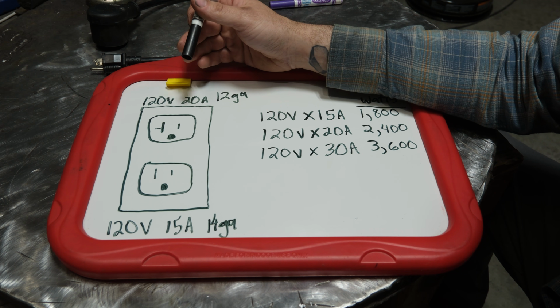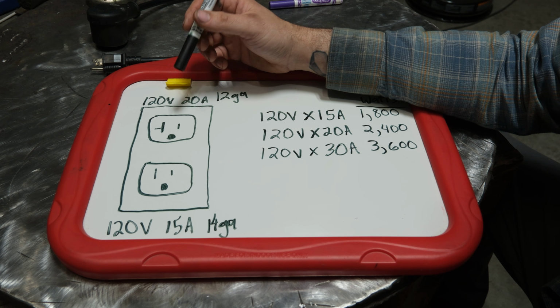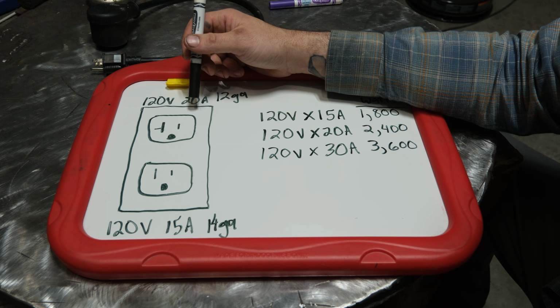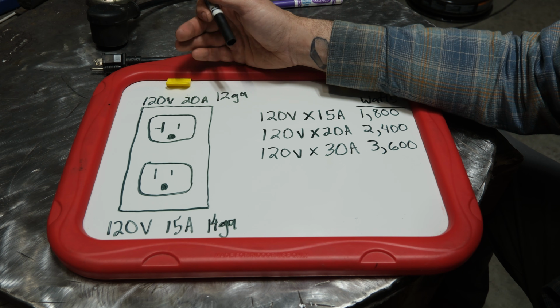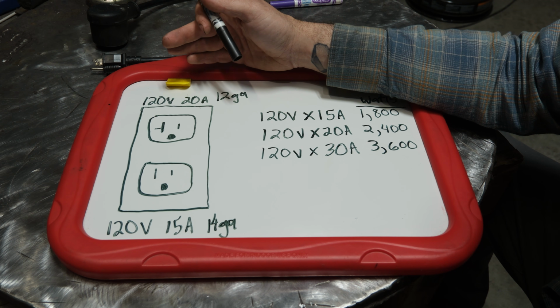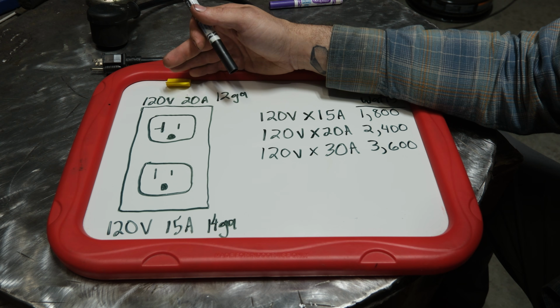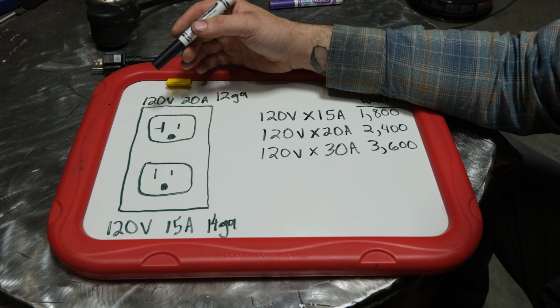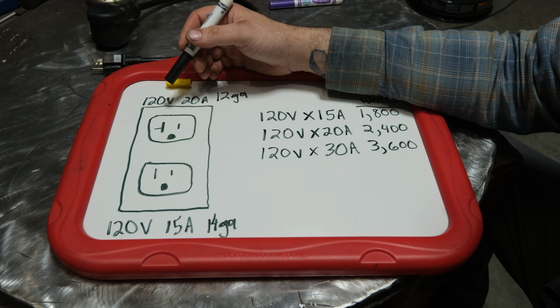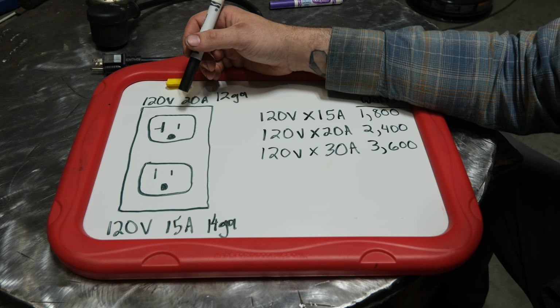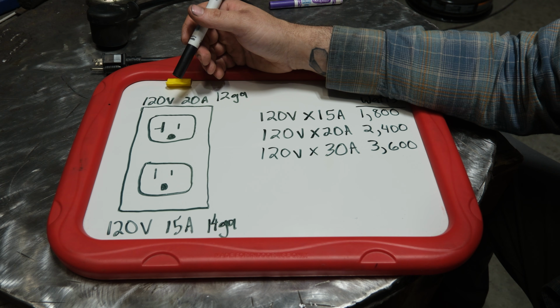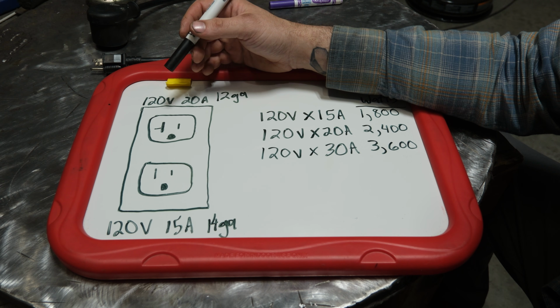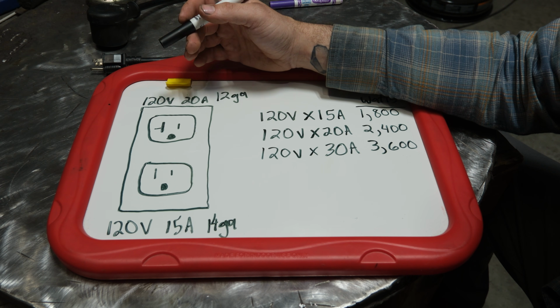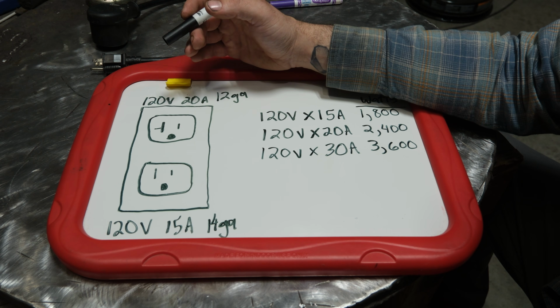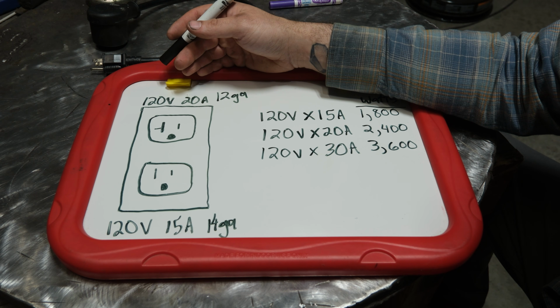So you need to verify what else is plugged into your 120 volt outlet before you go plug your welder in. The easiest way to do that is find the breaker for that, shut it off, and see what doesn't work anymore. If half your house no longer has ceiling lights and your outlet in the garage doesn't work, well, you're going to have a major issue in trying to weld anything off of that low of power, because everything combined with your welder will add to the drain that's on that breaker and will likely trip it.